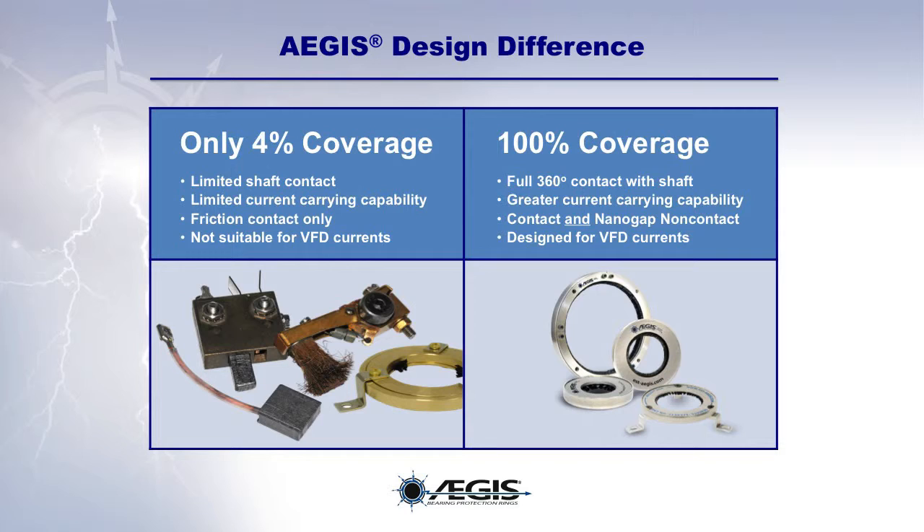Discrete point designs only offer limited shaft contact. Because of their limited shaft contact, competitive technologies have much lower current carrying capacities than the AEGIS rings. And while other shaft grounding technologies work only when they are in friction contact with the motor shaft, AEGIS rings work both when in physical contact with the motor shaft and when merely in nanogap proximity to it.